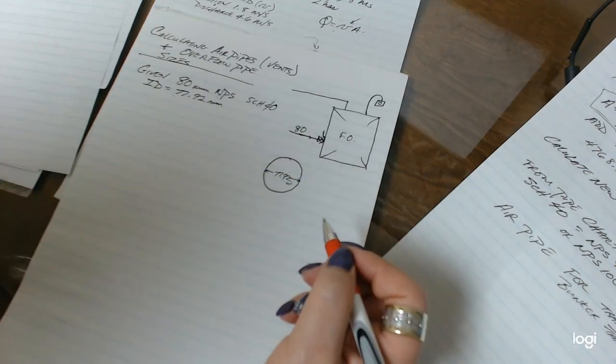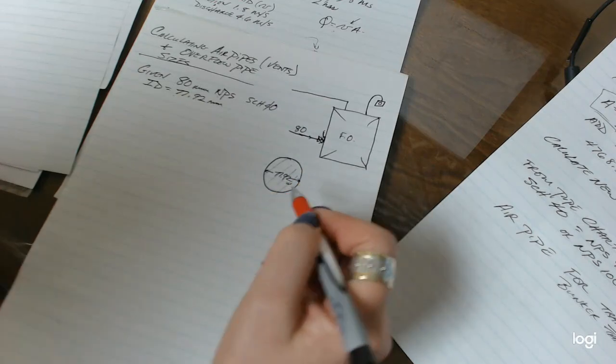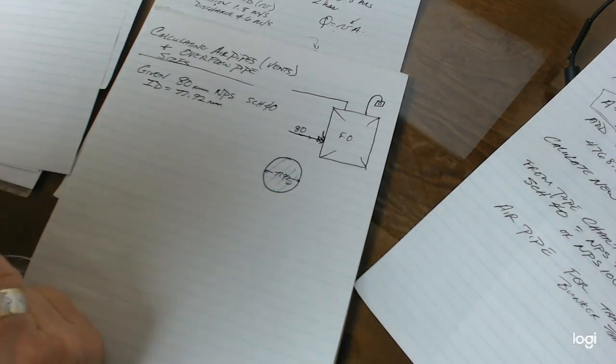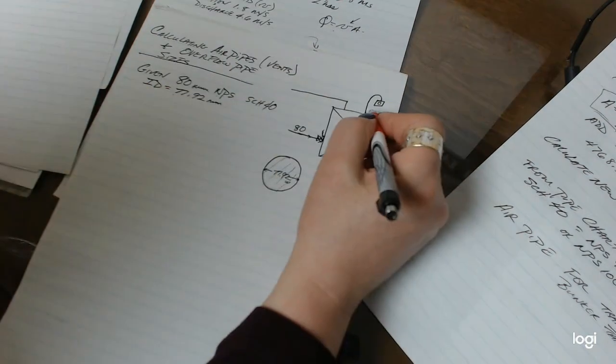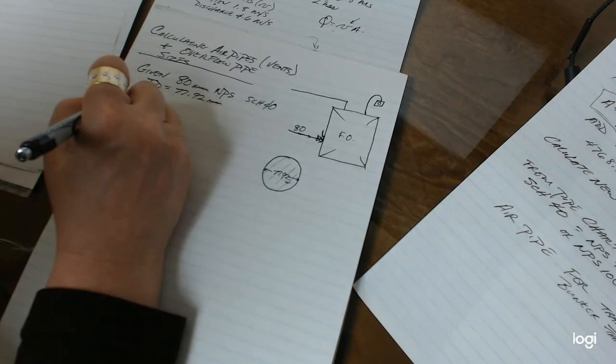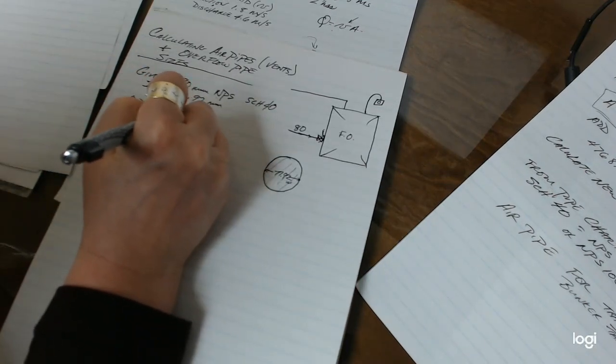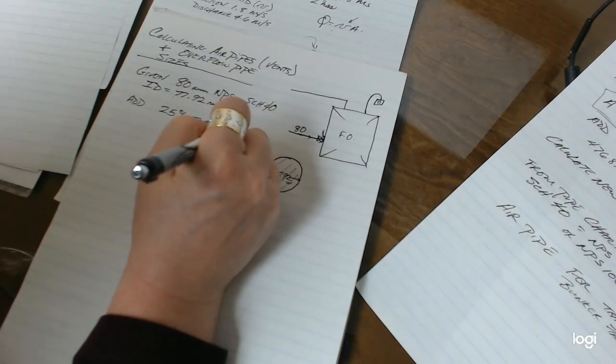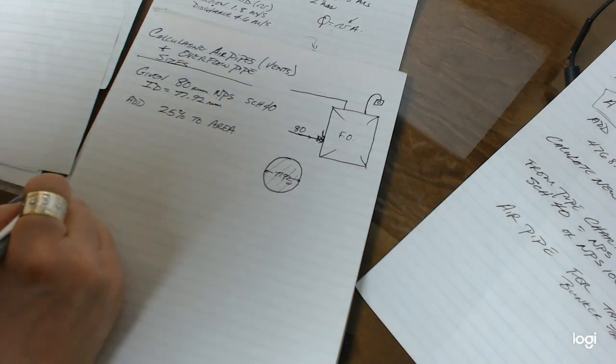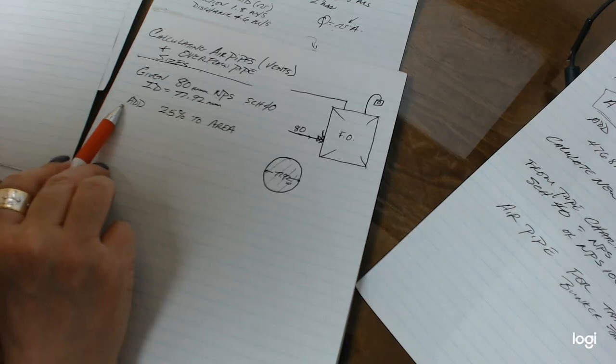In order for us to do the calculation on this, we actually had to look at the area of the circle that would be like taking a slice out of the pipe. Because according to the rules, in order to calculate the size for these two pipes, we actually have to add 25% to the area, to the area of the pipe. And if you want some clarification on this, you can find this in part 5 of Lloyd's Rules under Chapter 13.